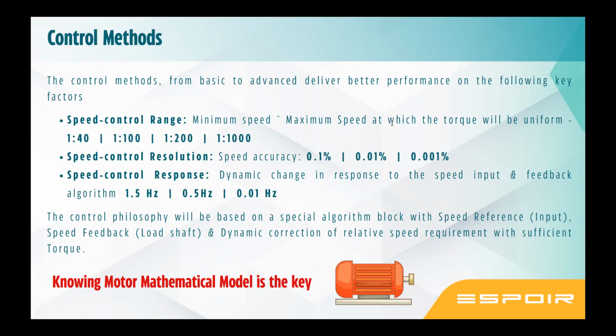Now in a car, you press an accelerator. What if it takes longer time to go to the speed? Means the command is given, but then it takes time to react. In VFD with an advanced control method, the response is going to be very quick. So the drive is going to give very quick commands in change of parameters like voltage, current, and all that. Whatever aspects it is delivering to the motor, it is going to dynamically change that. So this is what you achieve by adopting a better control method. Speed control range, speed control resolution, speed control response. So the key is knowing the motor mathematical model.